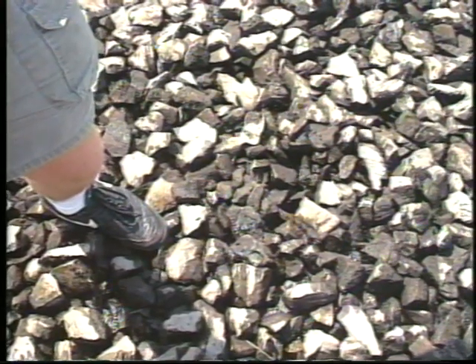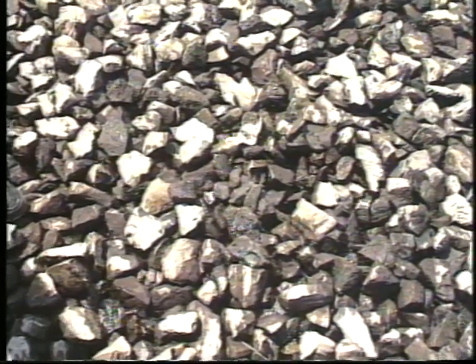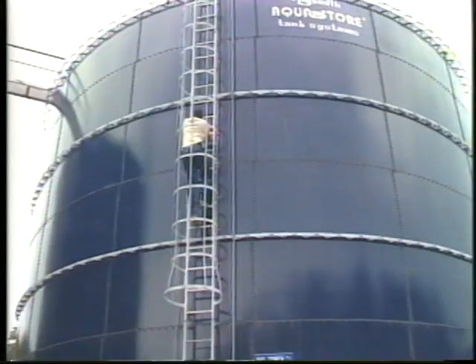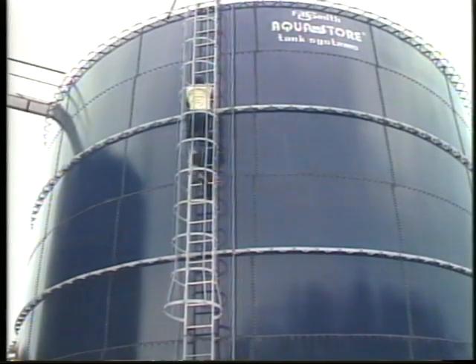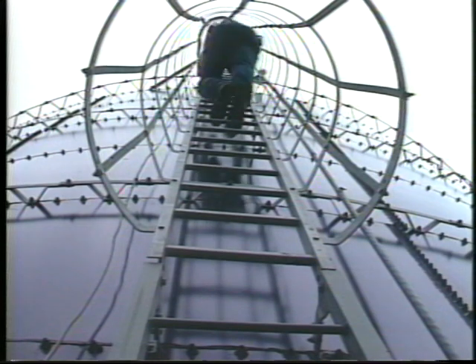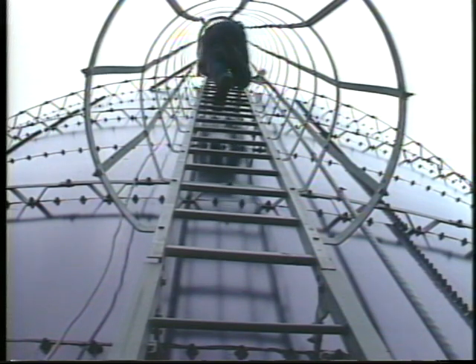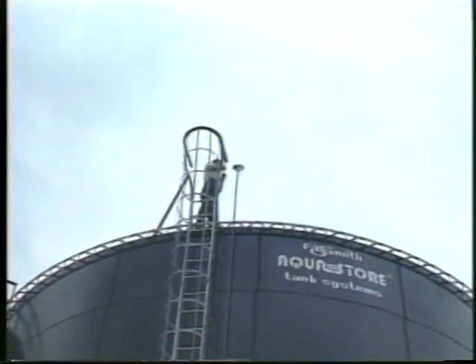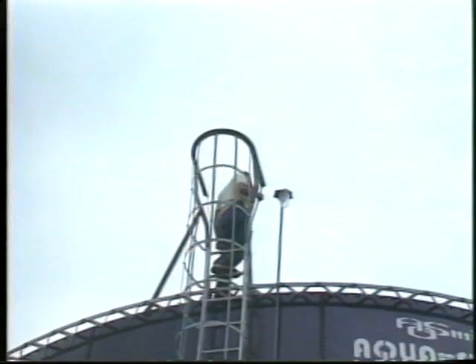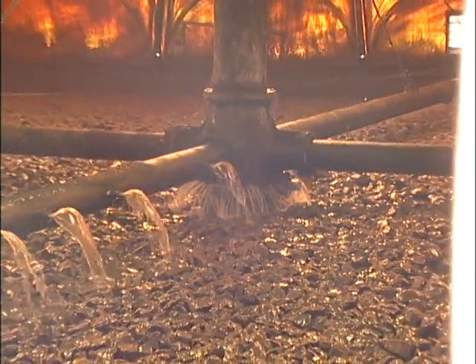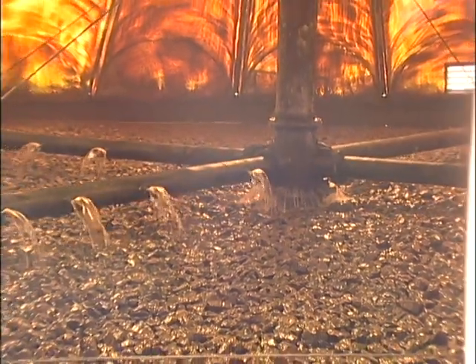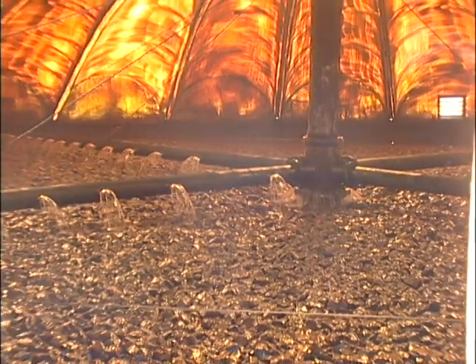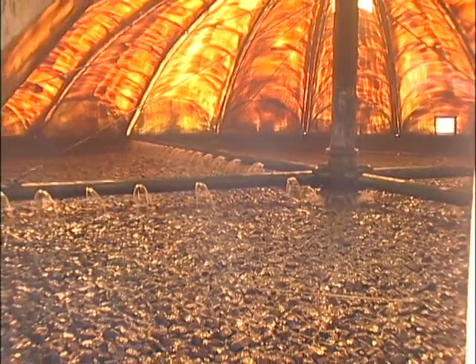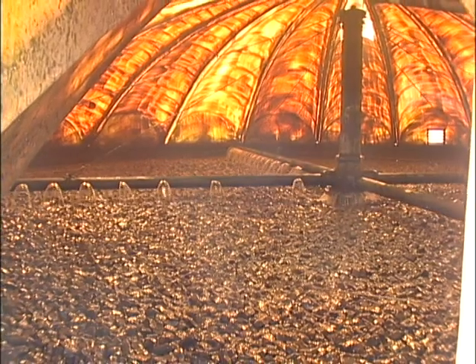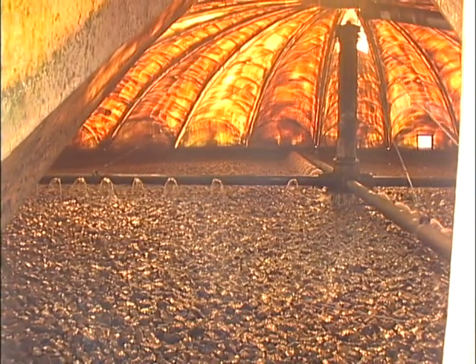Typical depth of rock media in a high rate filter is 3 to 5 feet, while synthetic media can be deeper than 40 feet. Some trickling filters that utilize synthetic media will have higher loading rates. These filters are sometimes referred to as super high rate filters. Roughing filters are essentially the same as high rate filters, except for receiving higher loadings. This type of filter is used primarily to reduce the CBOD to subsequent biological treatment units.